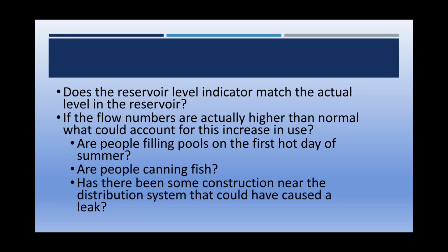But I think about a year later, we found that they had a leak in the line after we had run some swabs through the line to clean it. We began digging around and finally found the cause of this. The line that we had in the ground, even though it'd been there about 20 years, looked like when they were burying the line, somebody with an excavator had actually hooked the line and kinked it. But he didn't kink it enough to pull it out of the pipe in front of it. So there was no leak at the time.